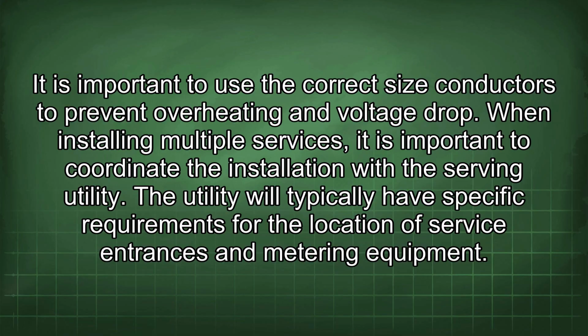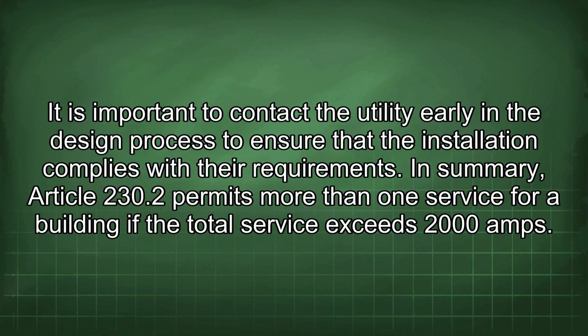When installing multiple services, it is important to coordinate the installation with the serving utility. The utility will typically have specific requirements for the location of service entrances and metering equipment. It is important to contact the utility early in the design process to ensure that the installation complies with their requirements. In summary, Article 230.2 permits more than one service for a building if the total service exceeds 2000 amps.